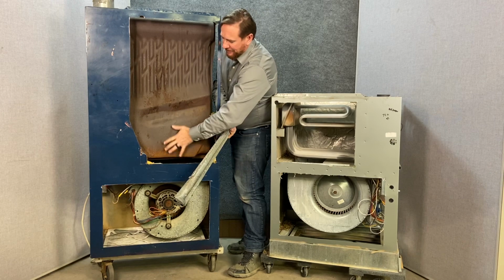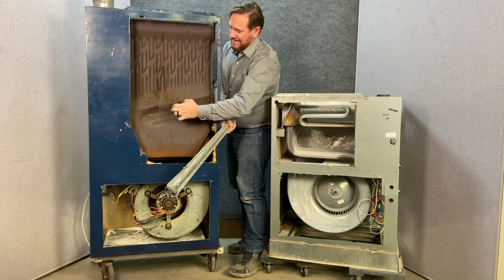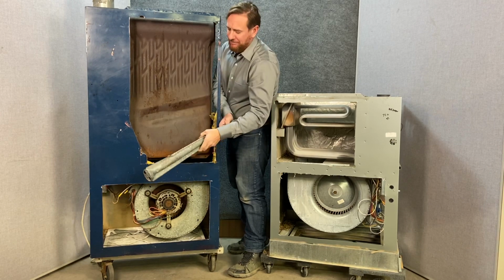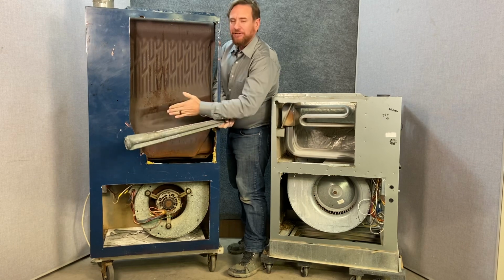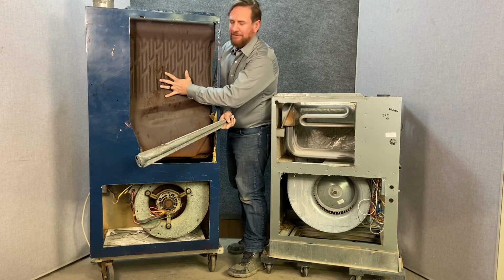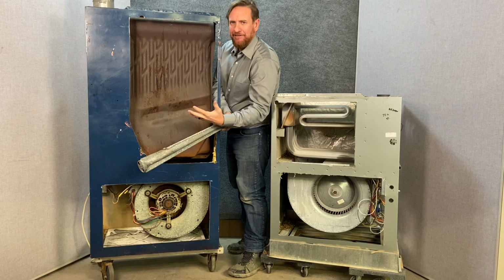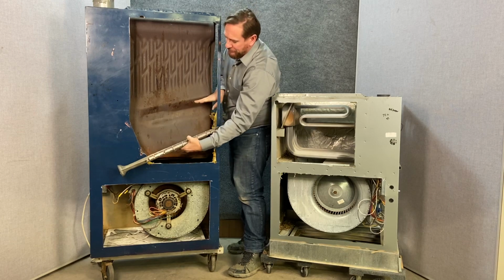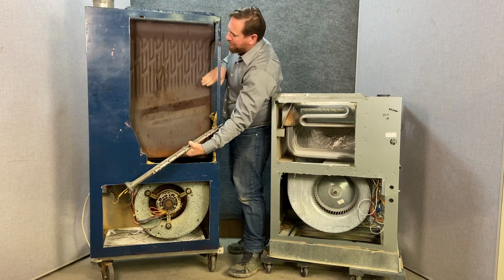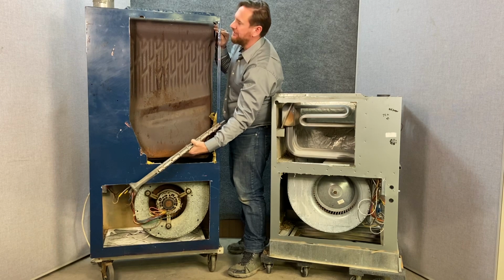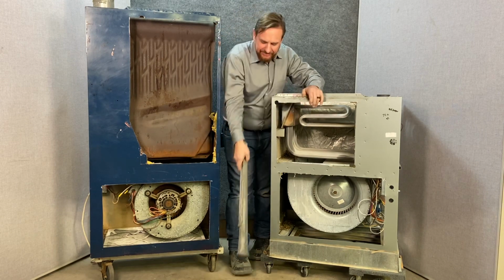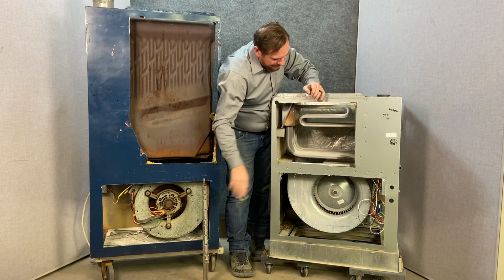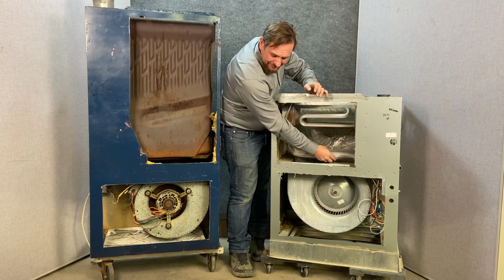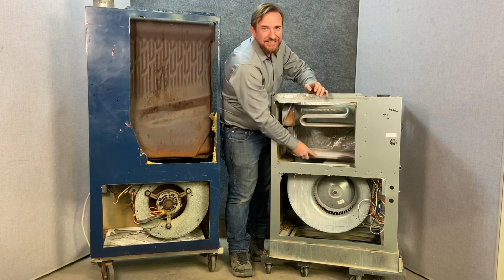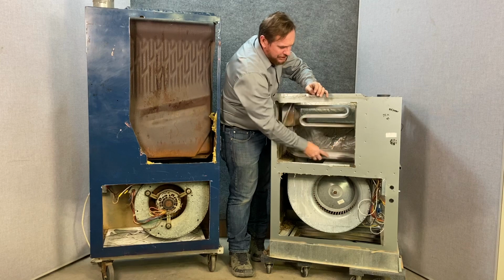So the air from the house is blowing over the outside of this, and inside this chamber, this heat exchanger, is where the flames are going to be burning. This keeps the flames and the gases separate from the air in the house. This would be the combustion side, but this whole entire thing is the heat exchanger side. On this one we have a very similar situation, except this side here is where flames burn. This is going to be our combustion chamber.